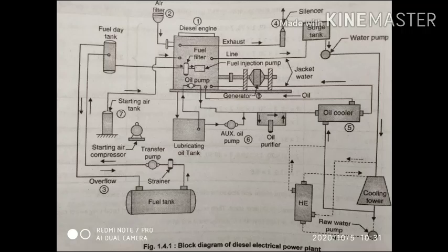In forced water cooling, cold water is sent through the cylinder jacket with the help of a pump. The hot water is cooled in a spray pond and recirculated. The water used for cooling the engine cylinder is softened by a water treatment or water filtration plant in order to avoid the formation of scales in it. This requires the control of the flow of cooling water according to the load on the engines.